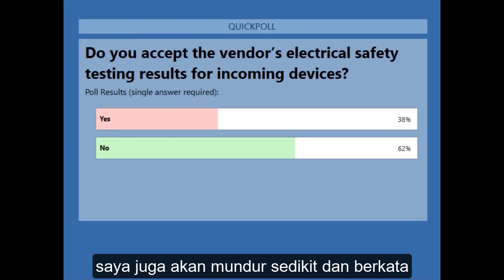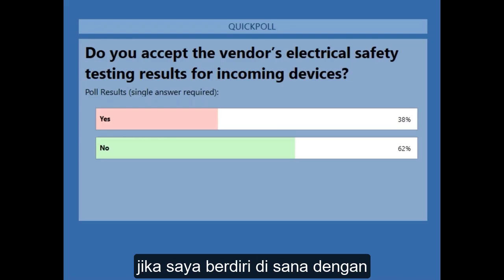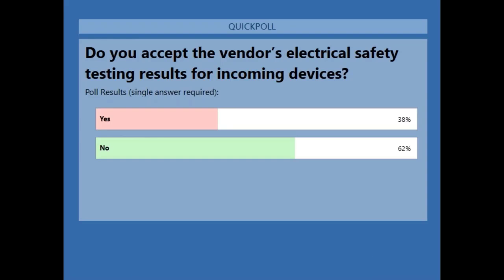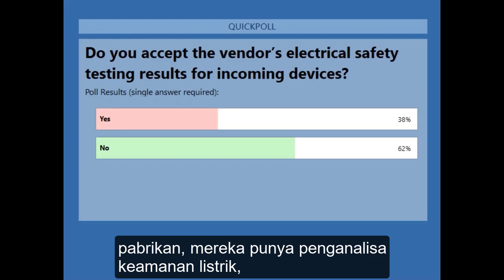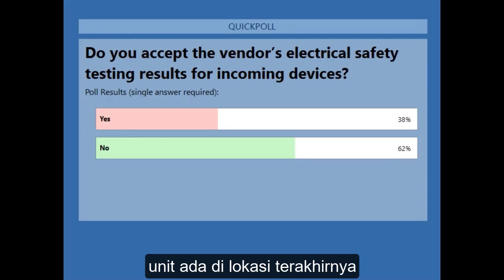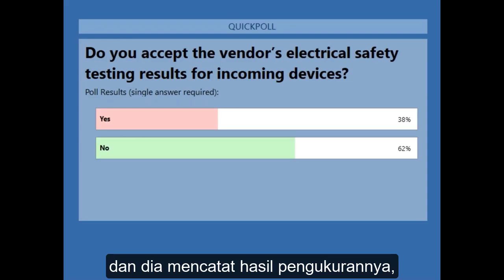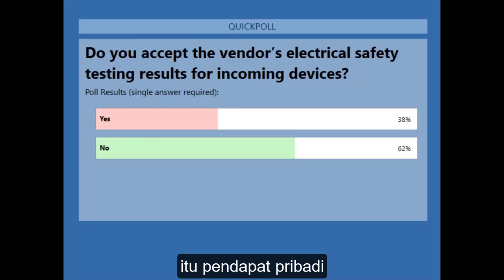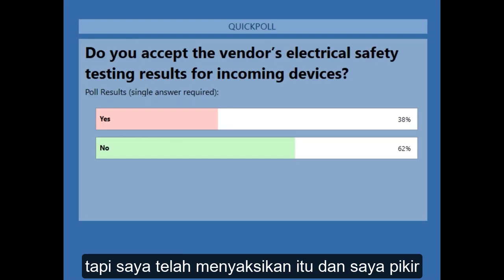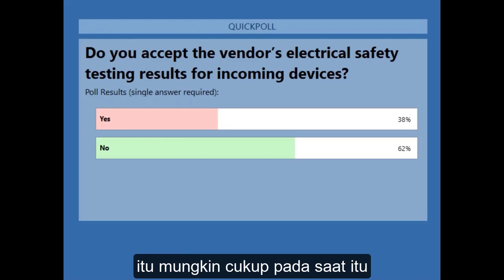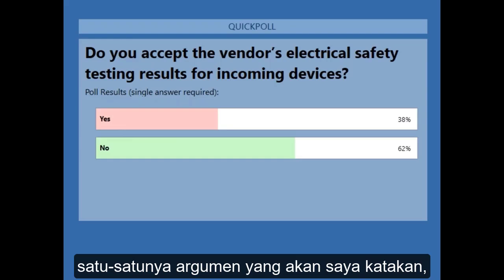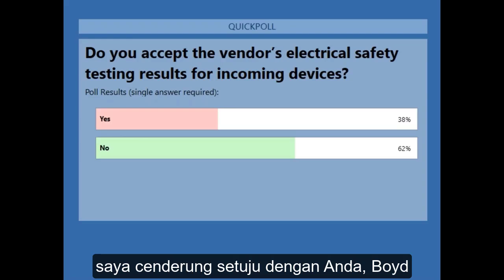On your incoming inspection, yes, you have to do that. Now, I will also back up a little and say, if I'm standing there with the manufacturer, he's got his electrical safety analyzer out, the unit's in its final location, and he puts down his values, I think that would suffice. That's a personal opinion, but I have witnessed that, and I think it would probably suffice at that point. The only argument I would say - I tend to agree with you, Boyd.